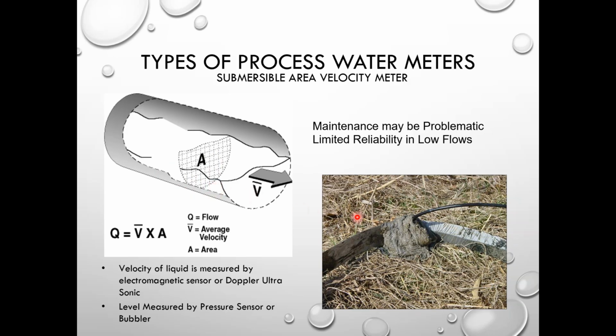With these sensors, they have to be maintained, of course, because you'll have sediment, silt, grease, solids, and rags that will generally come down and hit that sensor. These will work great in situations where you have large pipes with large volumes of water. These sensors are generally about 1 inch in height, so it requires that you have at least 1 inch of flow to record velocity.